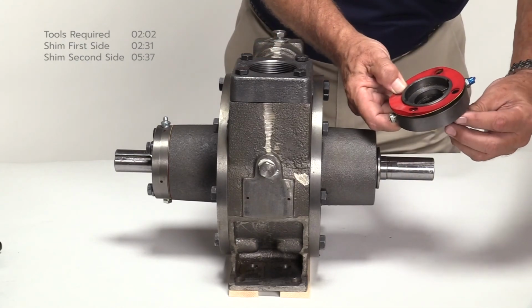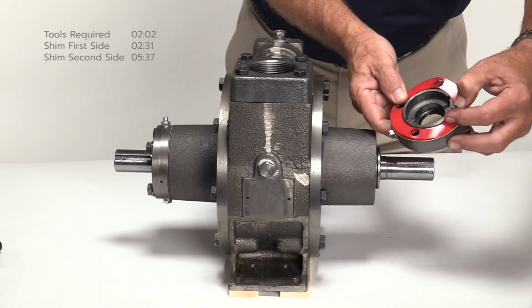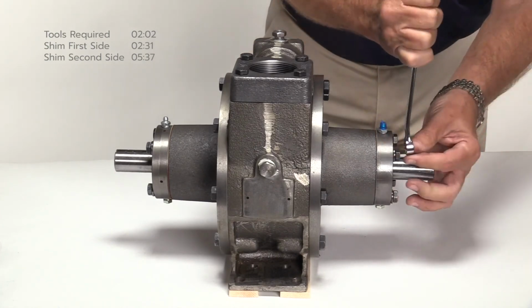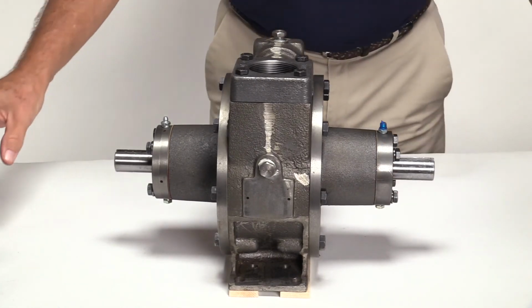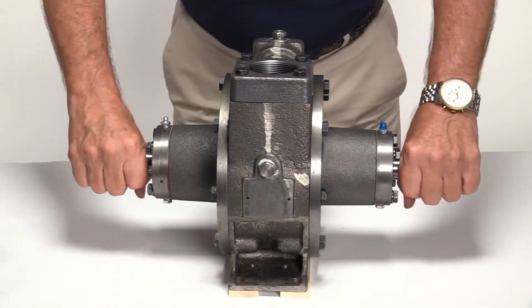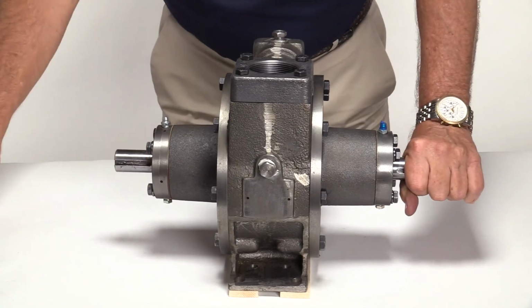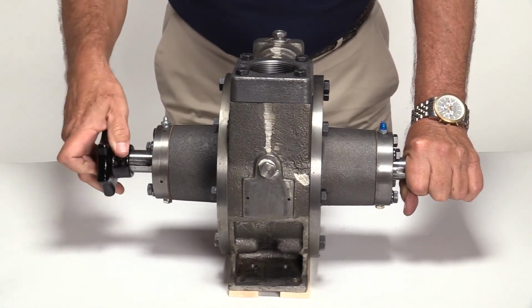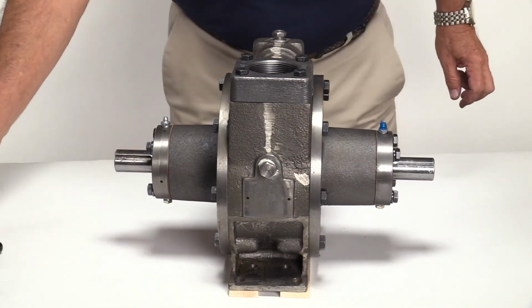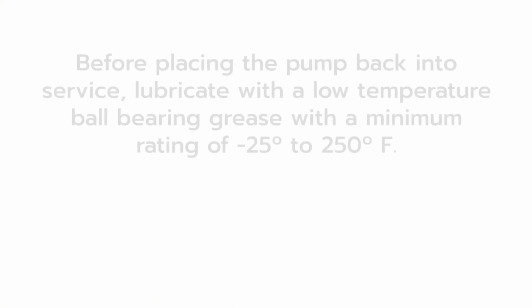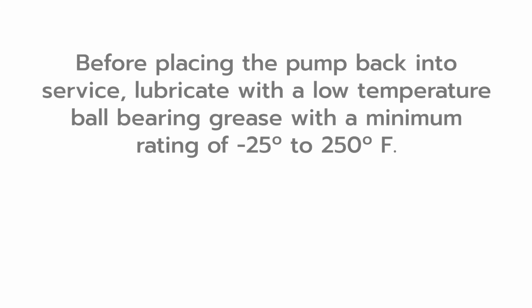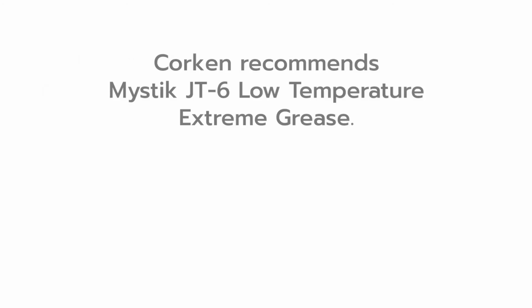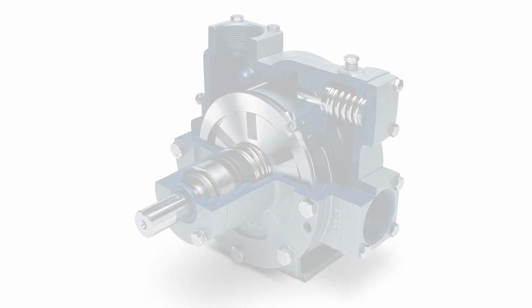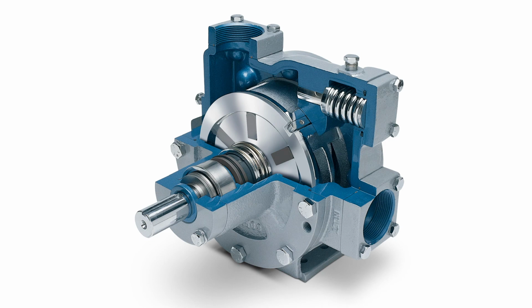To hold the shims in place, insert a bolt through one of the holes in the bearing cap and slide it over the shaft. Install the remaining bolts and tighten in a cross pattern to the torque value listed in the Installation, Operation, and Maintenance Manual. After the bearing cap has been secured, make certain the pump shaft turns freely by hand. Before placing the pump back into service, lubricate the pump with a low temperature ball bearing grease with a minimum rating of -25 to 250 degrees Fahrenheit. The lubricant used by Corken is Mystik JT-6 Low Temperature Extreme Grease. This completes the procedure for how to shim a Z-Series sliding vane pump.